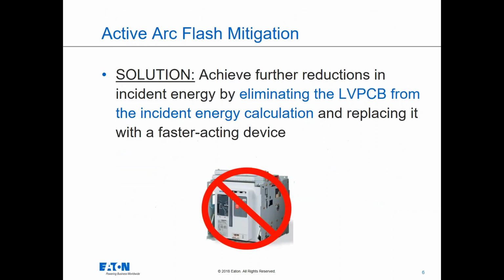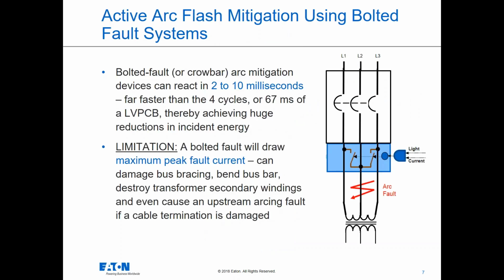go any faster. So if we had a solution that could hasten the response and work around the limitation of a circuit breaker's mechanism to speed up the reaction, then maybe we can further reduce the incident energy. Another method for that does exist in the market. There are a couple of manufacturers in the industry that build bolted fault, or what we call in industry crowbar devices, that do arc mitigation. That can react very quickly, much faster than a low voltage power circuit breaker.